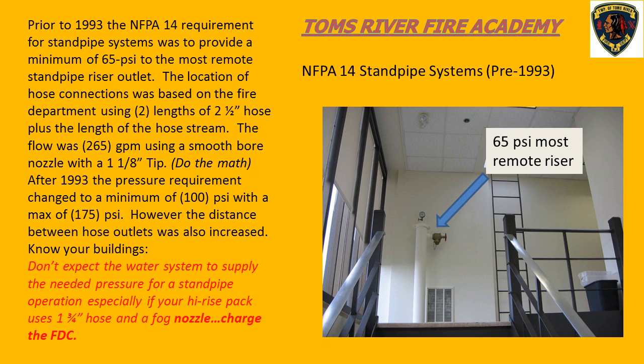We deal with standpipe systems. Prior to 1993, if it was a required standpipe system, the pressure at the topmost riser needed to be 65 psi. This requirement was based on the fact that the fire department was going to use 100 feet of 2.5-inch hose line plus a smoothbore nozzle with a 1 1/8" tip which flows 265 GPM. So this would give them the required flow off of the standpipe system.